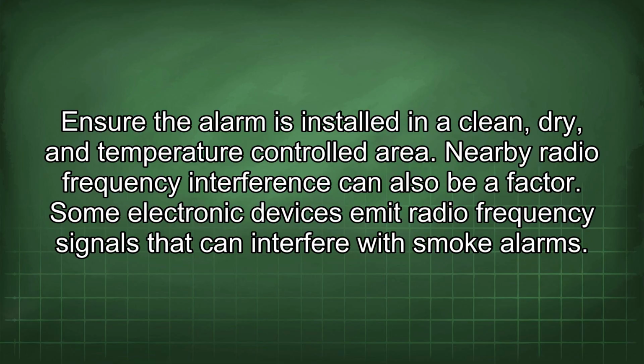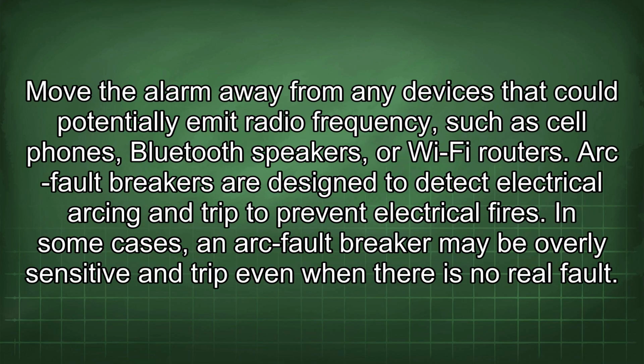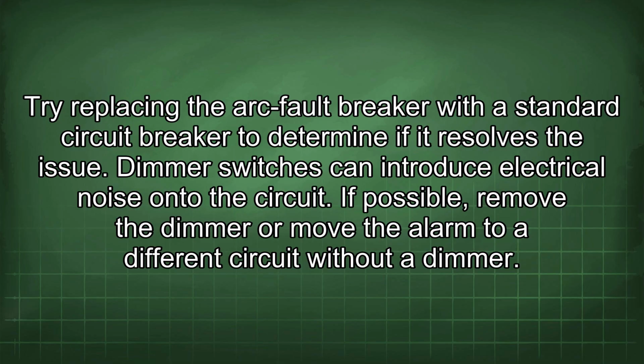Nearby radio frequency interference can also be a factor. Some electronic devices emit radio frequency signals that can interfere with smoke alarms. Move the alarm away from any devices that could potentially emit radio frequency, such as cell phones, Bluetooth speakers, or Wi-Fi routers. Arc fault breakers are designed to detect electrical arcing and trip to prevent electrical fires. In some cases, an arc fault breaker may be overly sensitive and trip even when there is no real fault. Try replacing the arc fault breaker with a standard circuit breaker to determine if it resolves the issue.